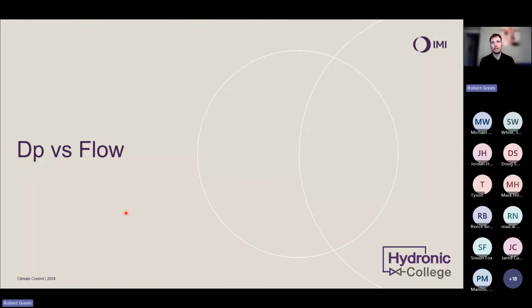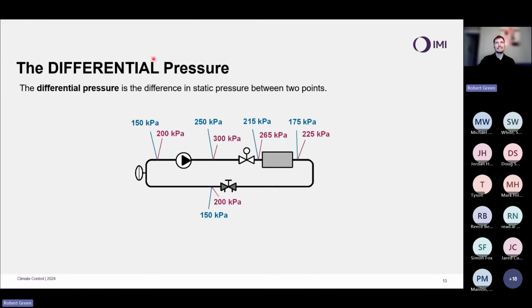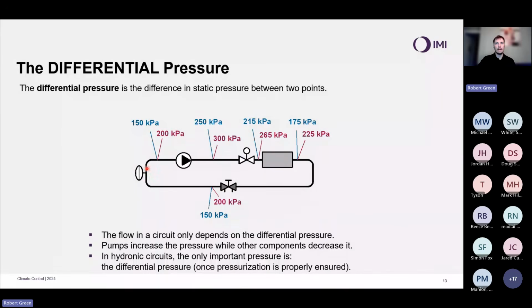Next, I want to actually look at flow itself and how flow is produced in a system. And really importantly, I want to put a large importance here on the differential pressure, with the differential pressure being the difference in static pressure between 2 points. So if we take this very simple loop here with a pump, a control valve, a terminal, and a balancing valve, we have a starting static pressure here that is set by my static pressure vessel on the inlet side of the pump. And here, the flow in the circuit is only dependent on the differential pressure. It is only the differential pressure in the circuit that does this, not the static pressure, the difference in static pressure. And in my system, pumps are going to increase that pressure while other components will decrease it.